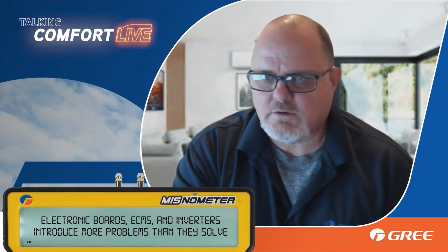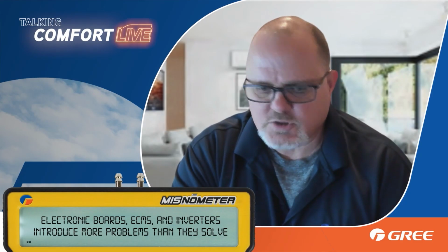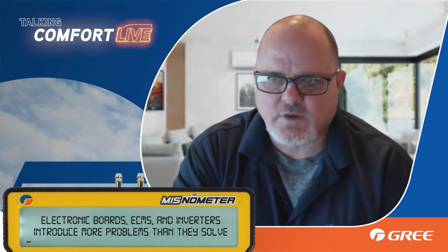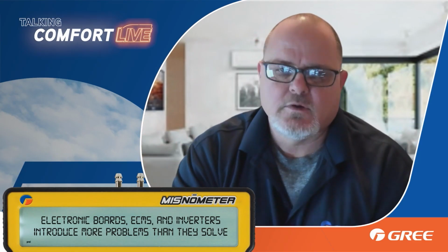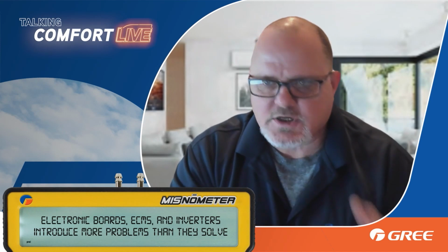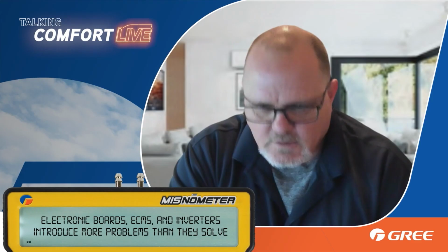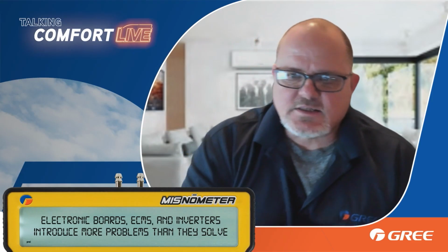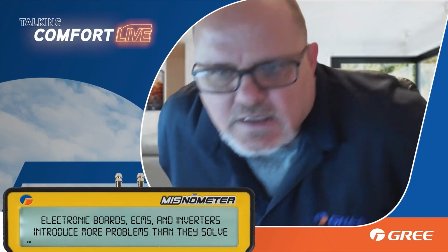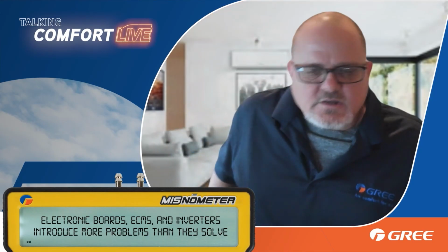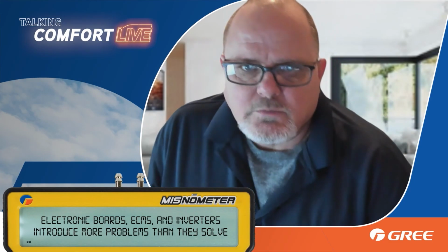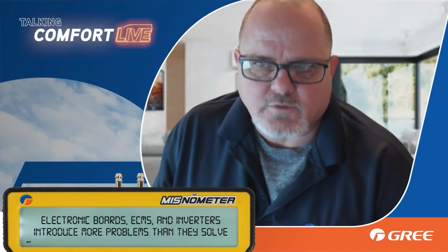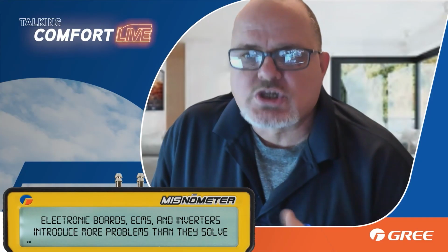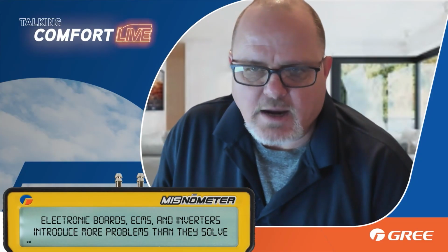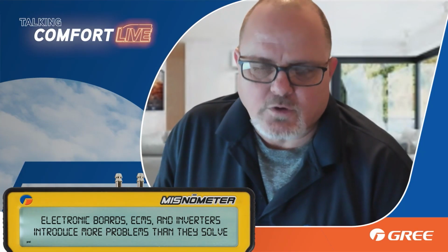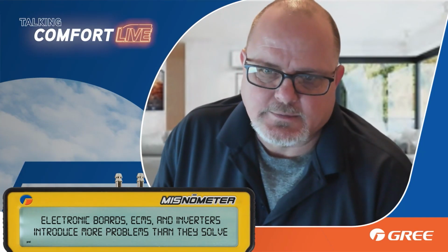You can still diagnose whether the compressor is locked up or not just by taking the amp draw on each wire. If we get some sort of amperage, 1, maybe 2 amps on each wire, but the compressor never actually starts and runs, then you've got a stuck compressor. We're not saying that with this equipment you'll never get a locked up compressor again. That's not true. It's a mechanical compressor, just like any other compressor. They can lock up. You're just never going to see that true locked rotor amperage because the inverter driver board won't allow it.